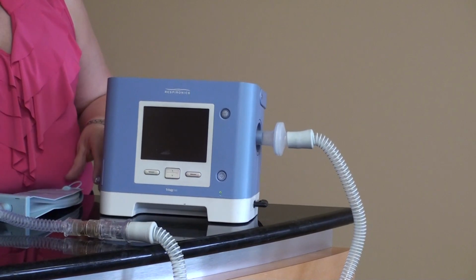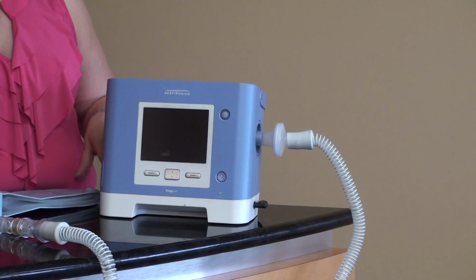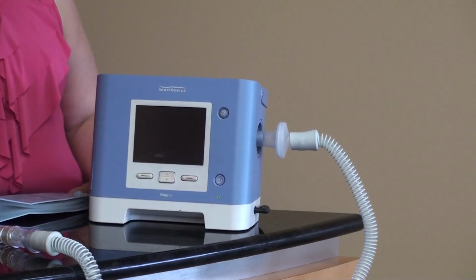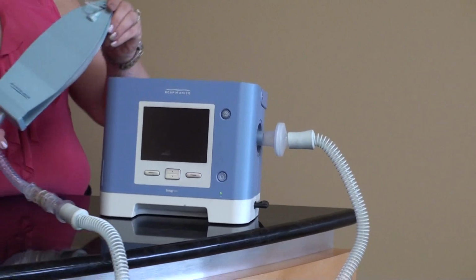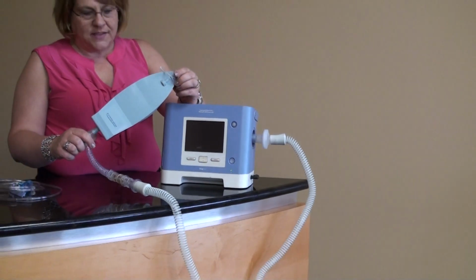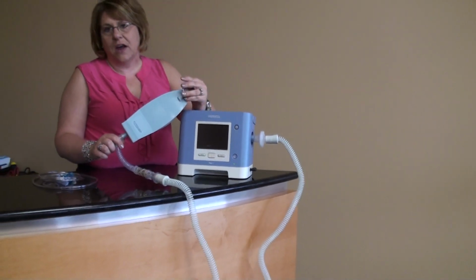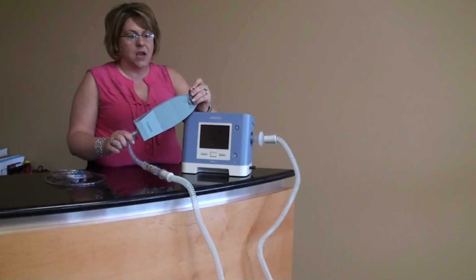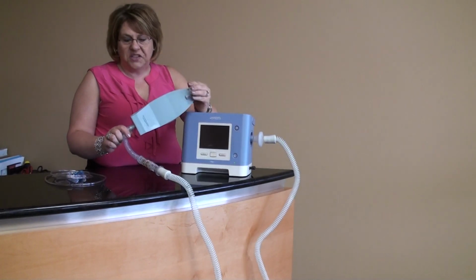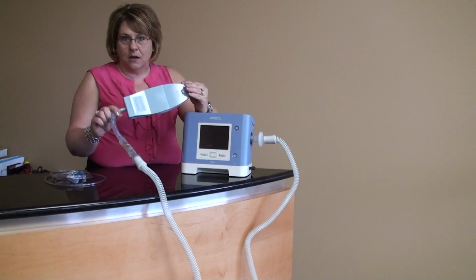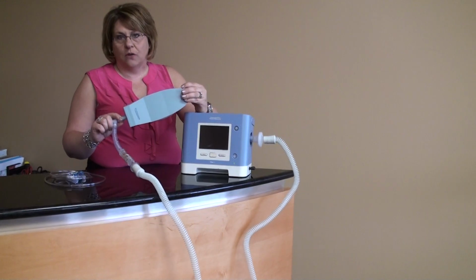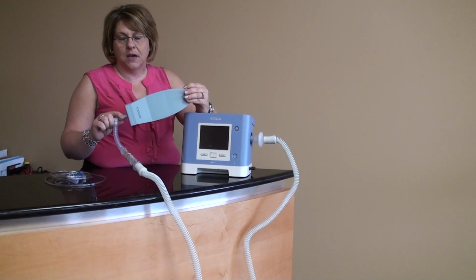So first of all, I want to remind everybody that when you turn on a ventilator, especially when it's off like this, when you first turn on a ventilator, make sure it is attached to your test lung. And the reason why I say that is because you never know if settings have gotten changed or things have gotten bumped or something's not going to be right with the ventilator. So you always start off by turning it on with the test lung, and then you put on your client once you are sure that the settings are okay and everything is working properly.